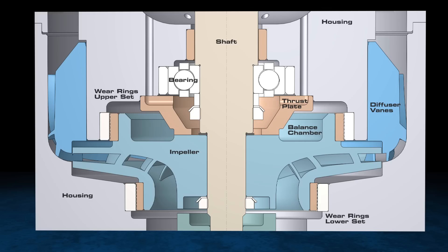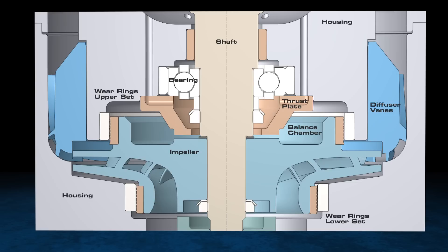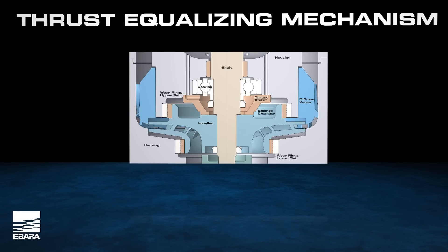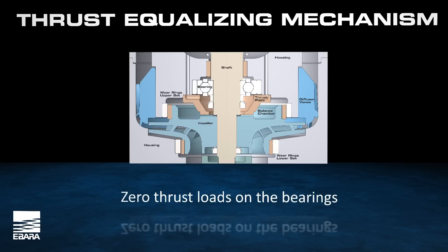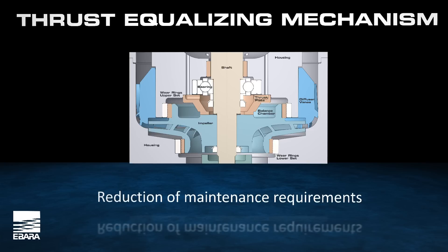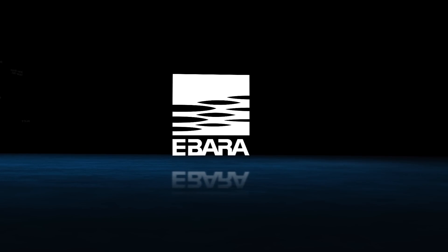All of Ebara's machines include the patented Thrust Equalizing Mechanism, or TEM. The TEM system eliminates all axial loads on the machine's bearings. The operation of the TEM is simple: while in operation, the TEM balances the pressure between the upper and lower impeller surfaces. This balance provides a stable system with zero thrust loads on the bearings, increased bearing reliability and lifespan, and reduction of maintenance requirements. This approach to thrust balancing has been demonstrated through thousands of hours of successful operation.